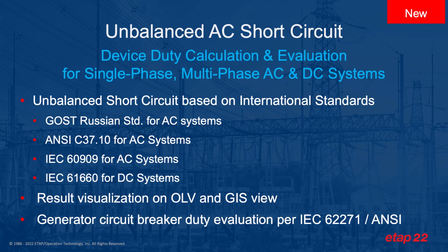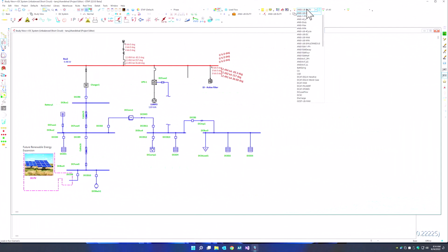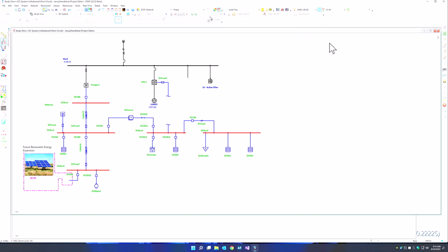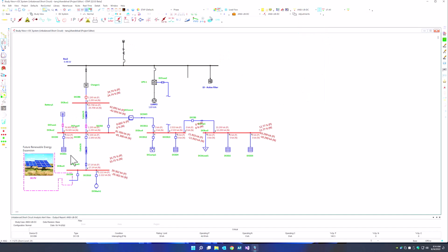You can have, of course, the result visualization on the single line diagram as well as the geospatial diagram, and the generator circuit breaker duty evaluation is also included per IEC 62271. In order to evaluate our DC short circuit, we can just simply run our DC scenario here, and you can see the short circuit simulation on the DC network, which is shown in blue, based on IEC 61660. And we can see the contribution, which is the forward current and the return current in our DC network, along with the phase contribution values and the voltages as well.